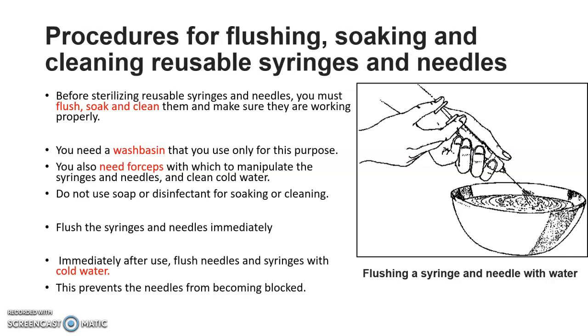And for cleaning, forceps are also used. First of all, we should not use soap or disinfectant during the flushing, soaking or cleaning. Then first step is flush the syringes and needles immediately after use. We should flush the syringes and needles in cold water. This may prevent the needles from becoming blocked.